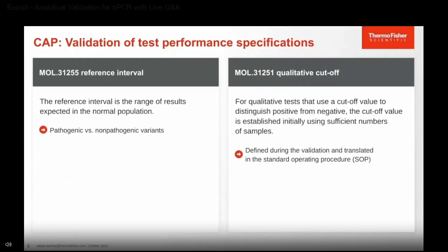For reference interval, it refers to the range of results expected in the normal human population. For qualitative cutoffs, this applies to tests that use a cutoff value to distinguish a positive from a negative sample. The cutoff value is established initially using sufficient numbers of samples, defined during the validation, and then translated into your standard operating procedures.